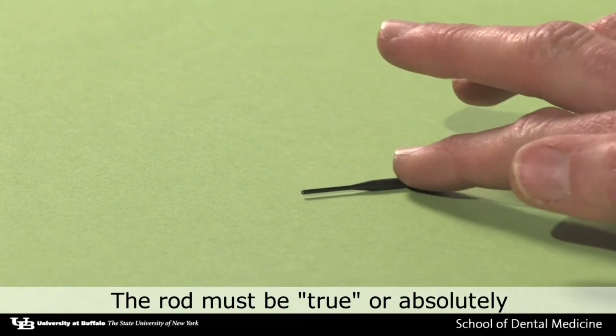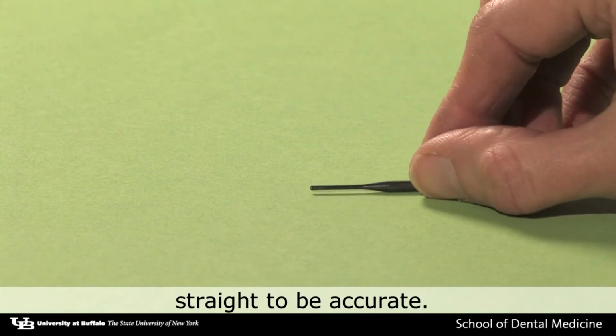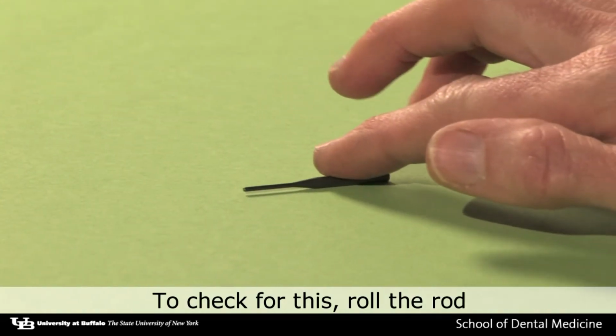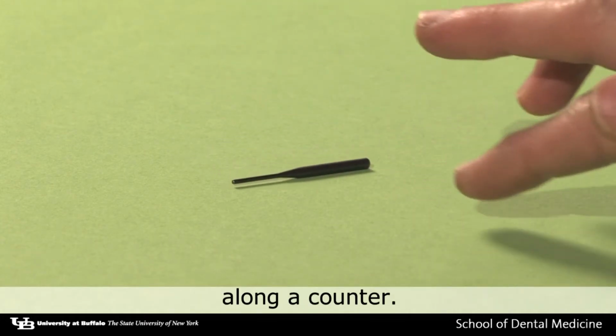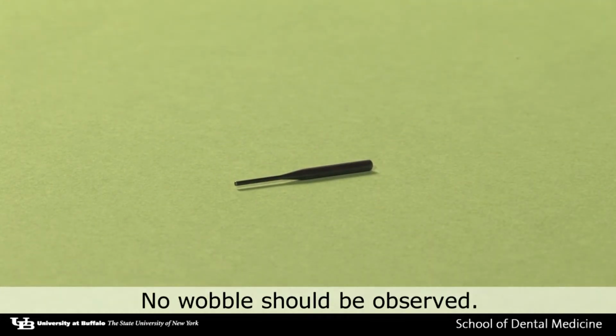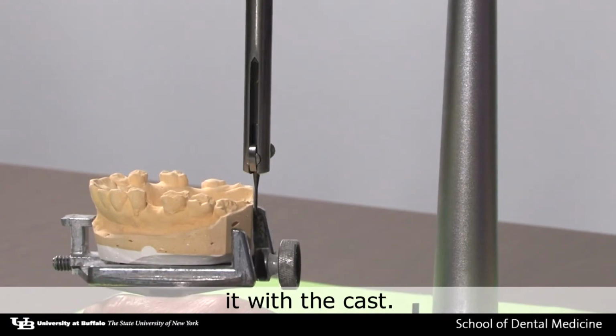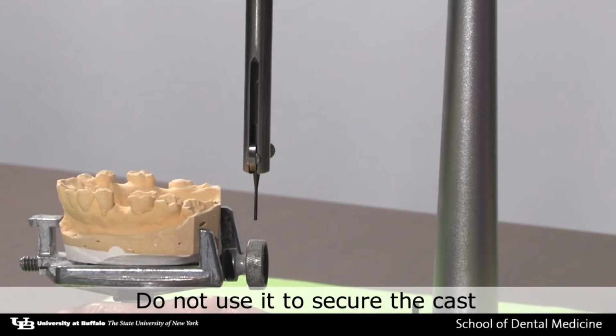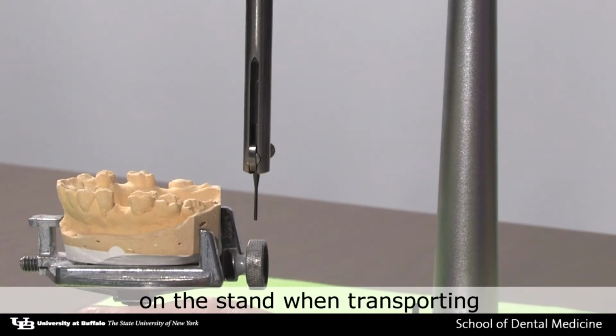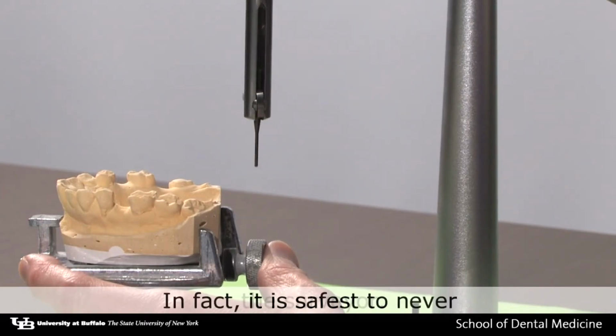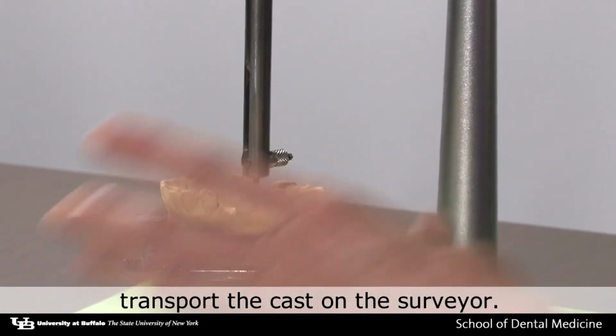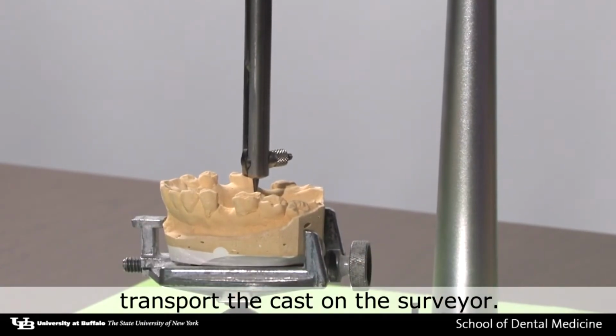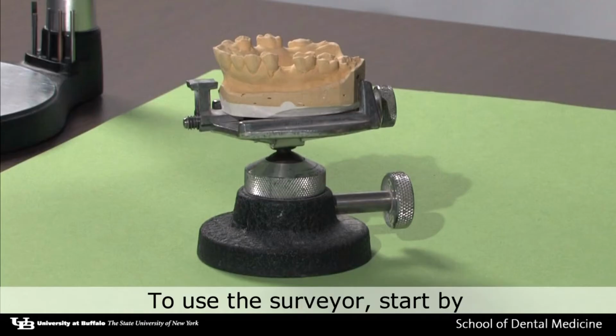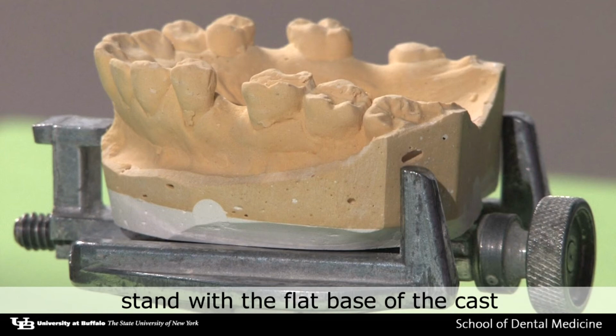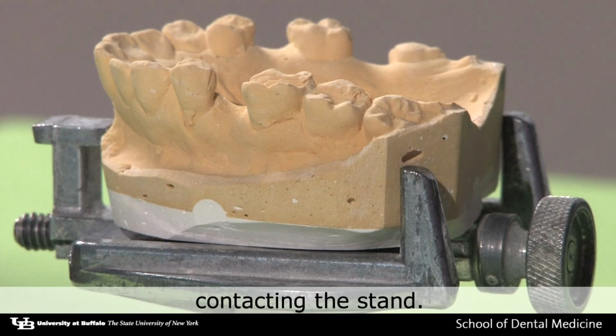While the analyzing rod is quite rigid, it is possible to bend it. The rod must be true or absolutely straight to be accurate. To check for this, roll the rod along a counter. No wobble should be observed. To safeguard the rod, do not bump it with the cast. Do not use it to secure the cast on the stand when transporting the surveyor. In fact, it is safest to never transport the cast on the surveyor. To use the surveyor, start by securing the cast to the surveyor stand with the flat base of the cast contacting the stand.